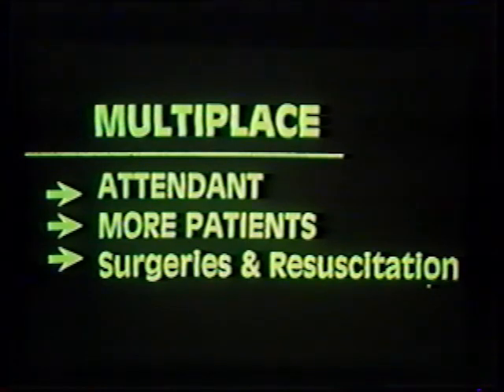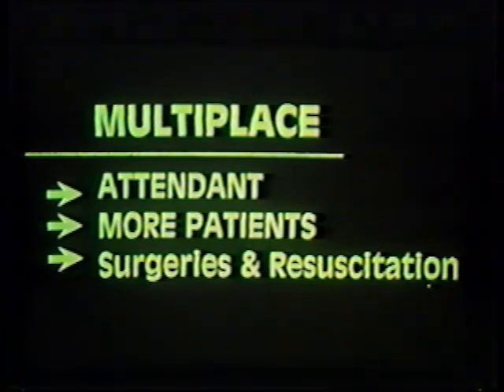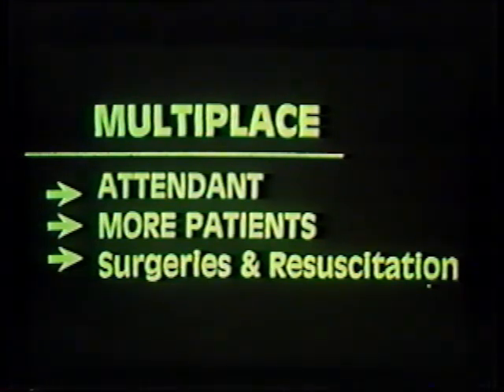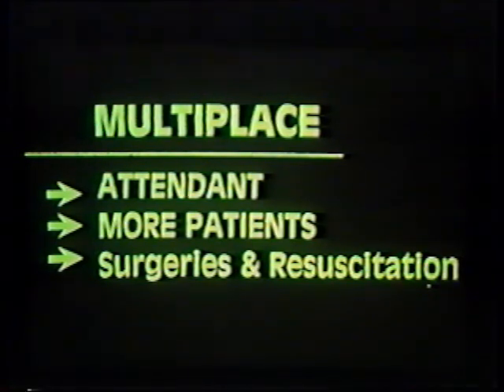We have to make a basic choice between the multi-place chamber and the mono-place chamber. Multi-place means that more than one person can be put in the chamber at a time, and mono-place means a single patient chamber. The multi-place chamber has the advantage of having an attendant with the patient at all times — hands-on treatment is possible. You can also treat more patients at the same time. In our facility in Milwaukee, we can treat up to five patients simultaneously.